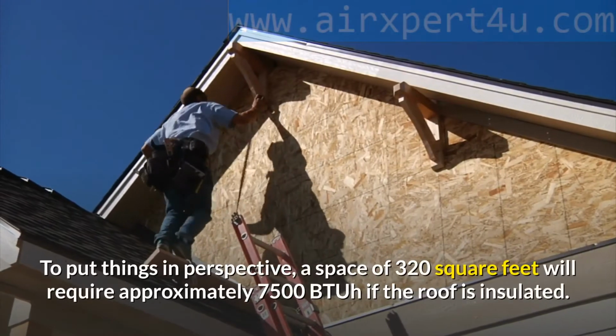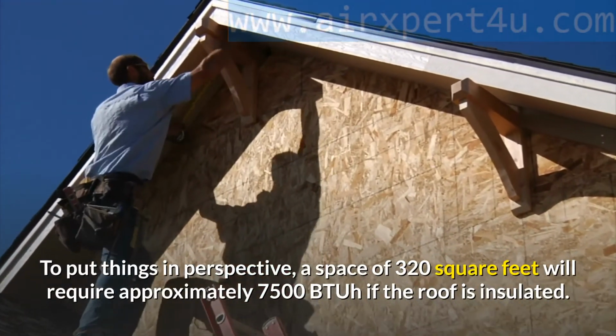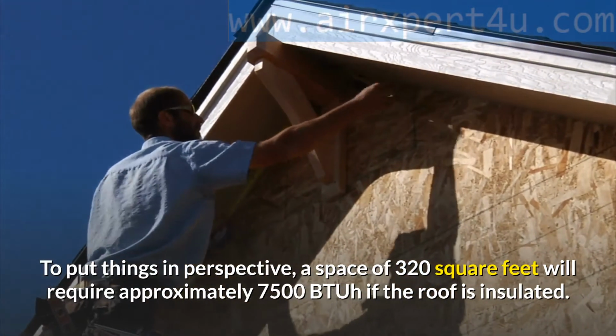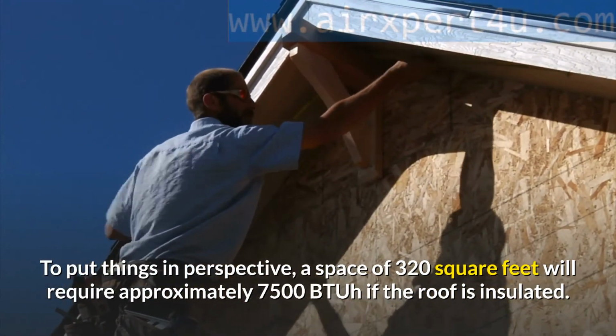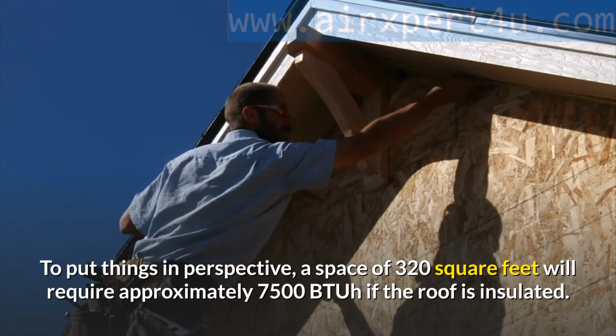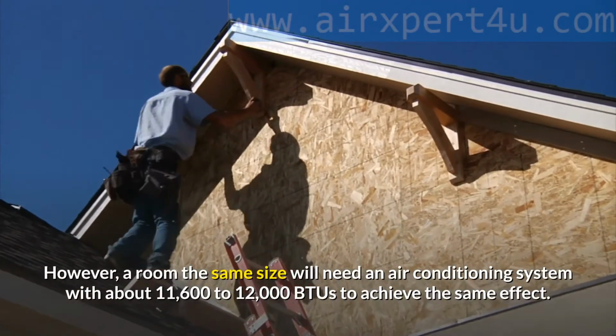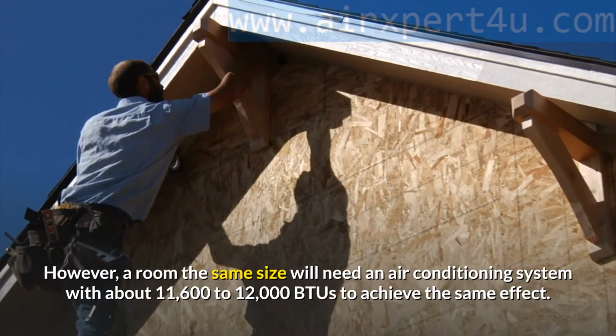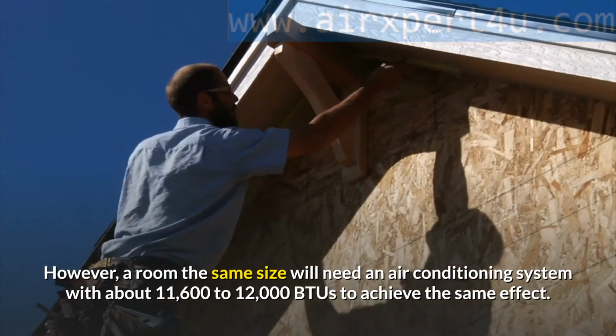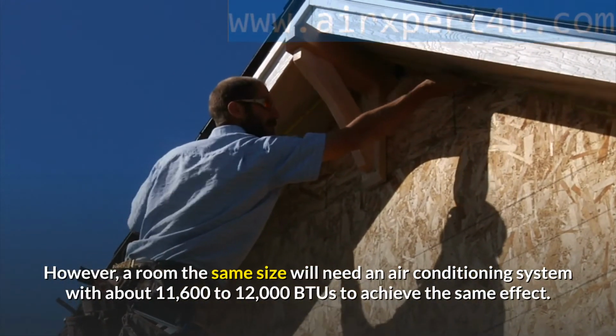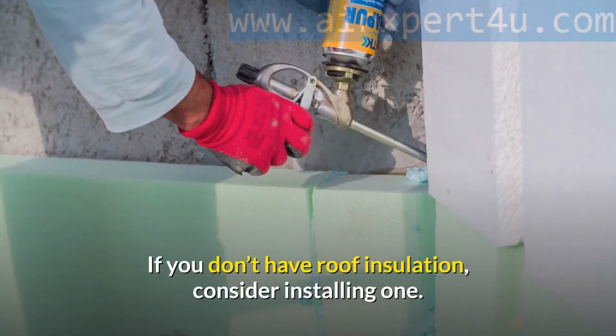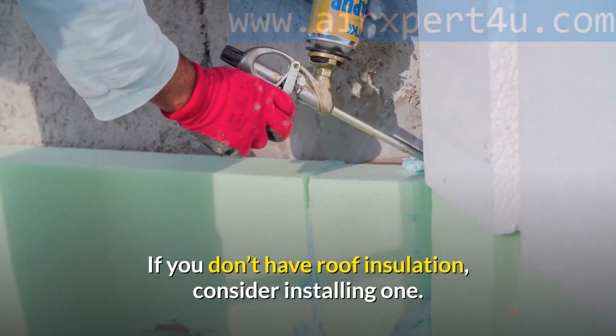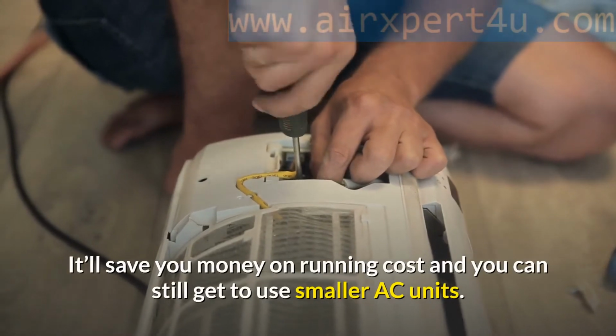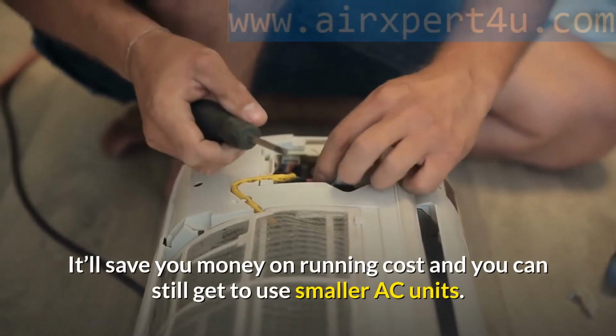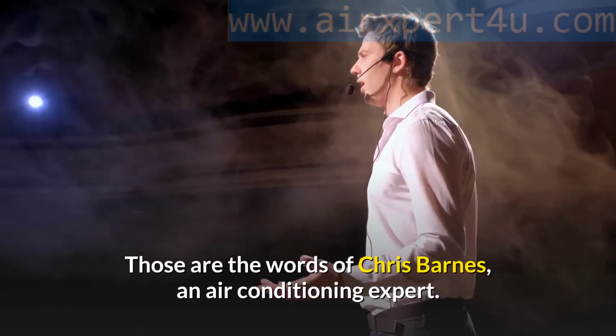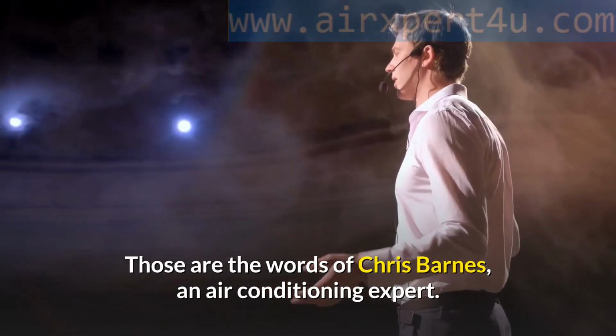To put things in perspective, a space of 320 square feet will require approximately 7,500 BTUH if the roof is insulated. However, a room the same size will need an air conditioning system with about 11,600 to 12,000 BTUs to achieve the same effect. If you don't have roof insulation, consider installing one. It'll save you money on running cost and you can still get to use smaller AC units. Those are the words of Chris Barnes, an air conditioning expert.